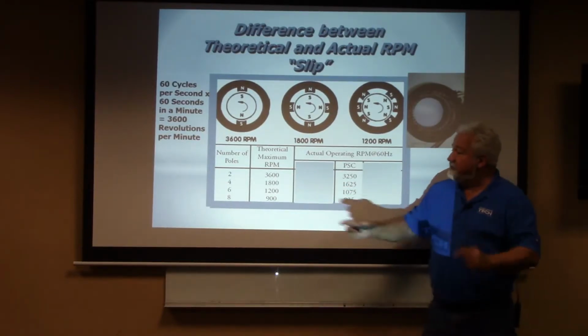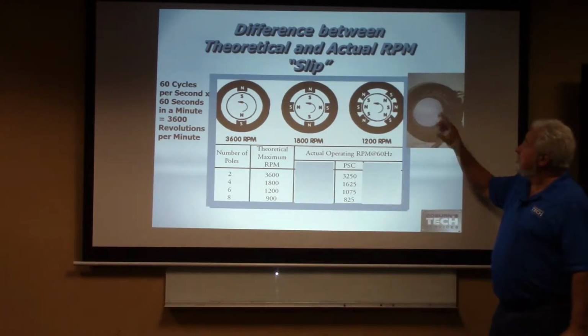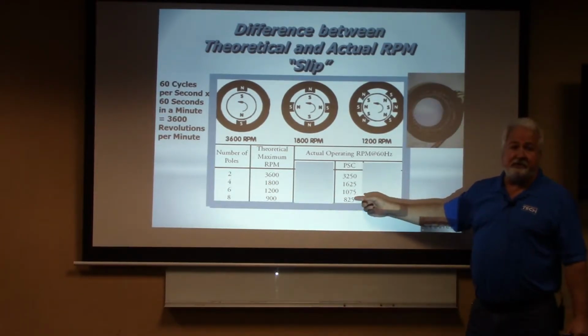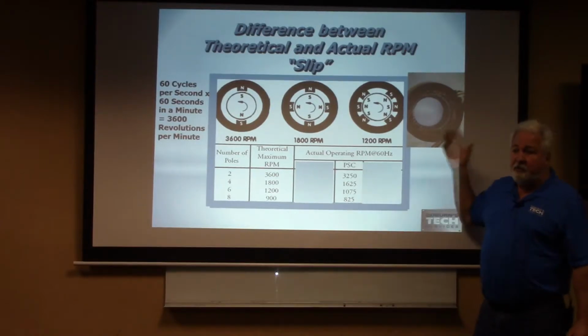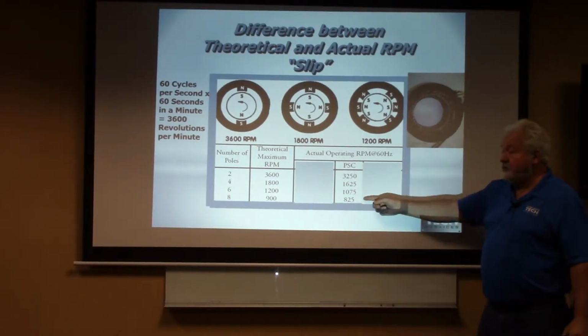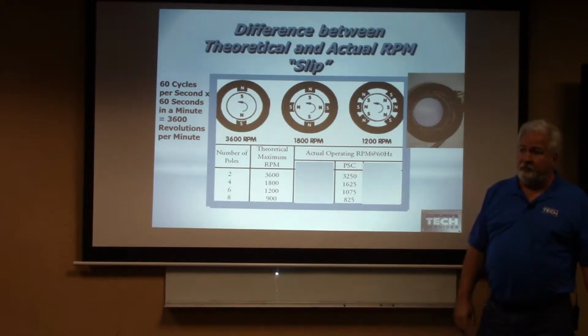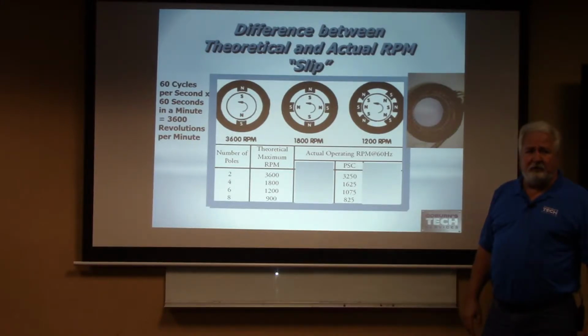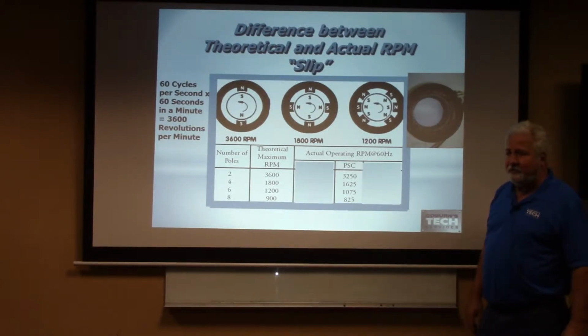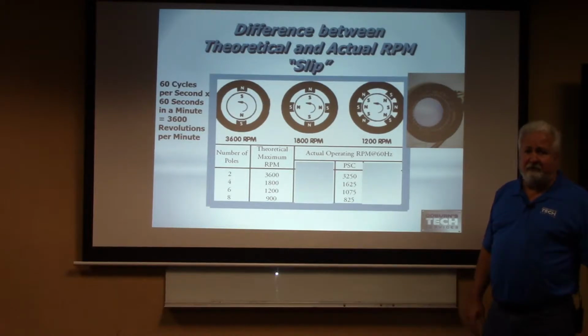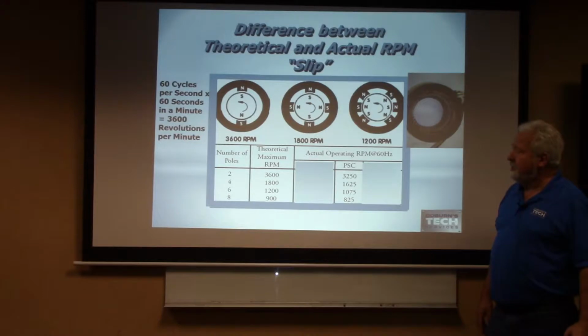So when you guys are seeing 6-pole motors out there, if you open up the end of it and see 6 poles, you know it's a 1075 motor. If you open up the back of it and you see 8 poles in there, you know it's an 825 motor. Easy enough? Good. It helps you on those jobs. The wiring schematic is always on there. It never burns off. Is that right? So you know what's going on that motor all the time. You know exactly what kind of motor it is. So sometimes you may need to pop off the end of it to see whether it's an 825 or a 1075 motor. Cool? All right. Well, that'll do it for you.